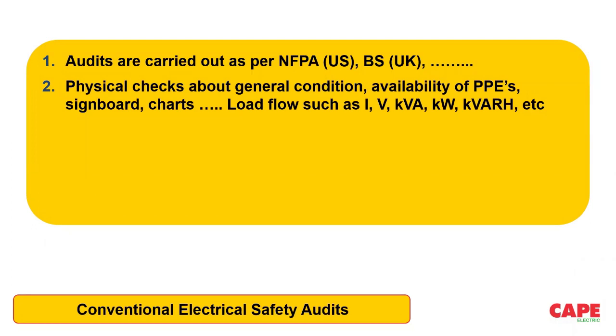Mostly the auditors, I don't use the word verification here because conventionally we are only doing audit. We don't have the habit of making verification. Conventionally, the auditors are doing some kind of physical check. They walk around the installation, find out whether any hanging cables, dust on the panel boards and so on are there. Then they check the general condition, availability of PPEs, signboards, circuit charts, tables, and so on. Plus, in some cases, the load flow analysis is also made, like the used power, the reactive power, and so on. But please note that load flow analysis is not a safety subject, it is something else.